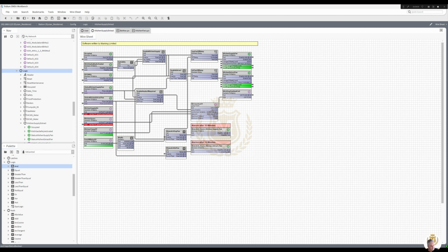So all we've got here is this AND gate with 3 inputs in there, and we enable the supply fan, output there. We have supply fan status coming in there that we've got a flow. Because we've got a flow, and again we've got the enable from there, we'll put the extract fan on. And then when we've got both extract fan and the enable, we can use the heater if required.